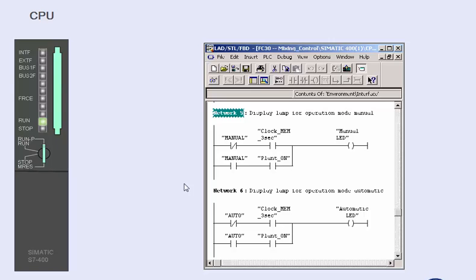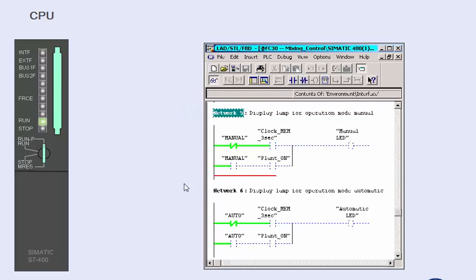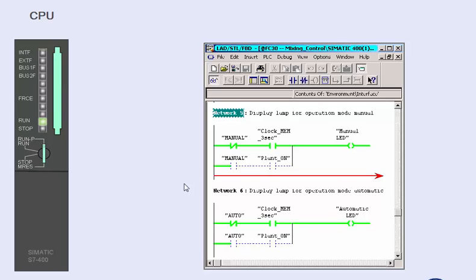You activate the program status function via the monitoring button in the toolbar. In the program status, the editor constitutes the active binary program flow with a selectable color, green in this example, and shows the current signal status of the operands.